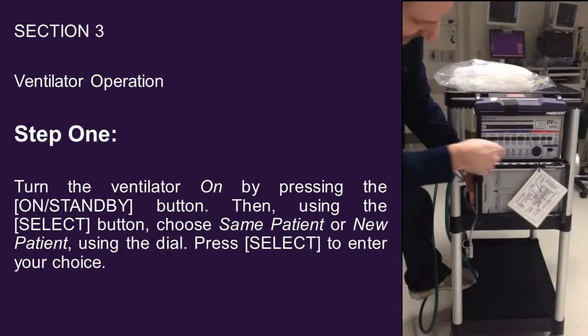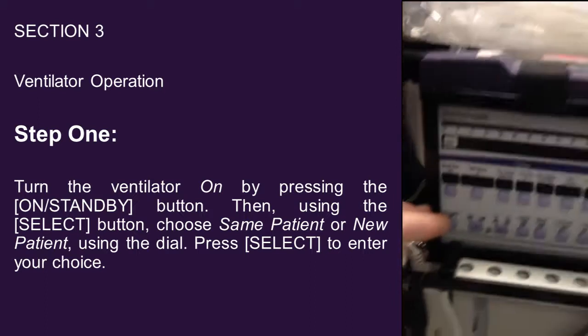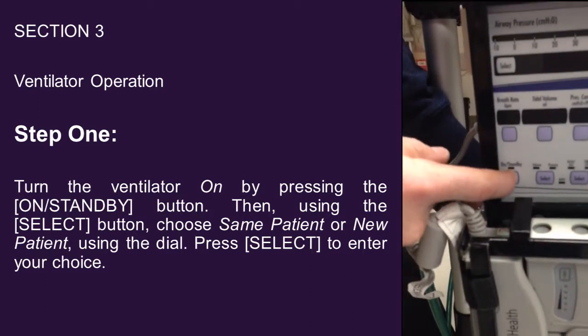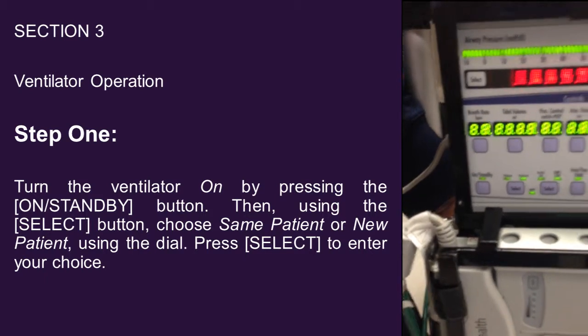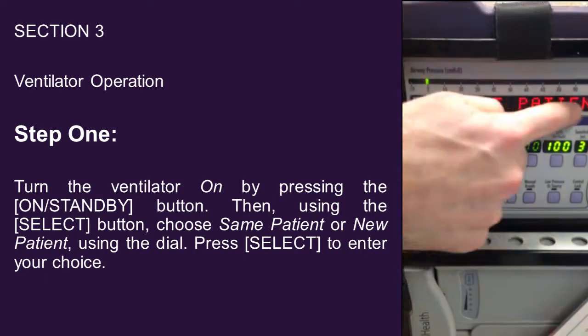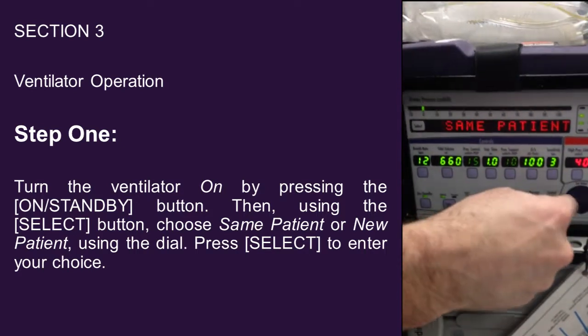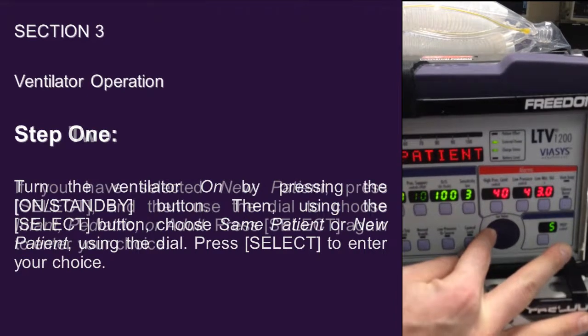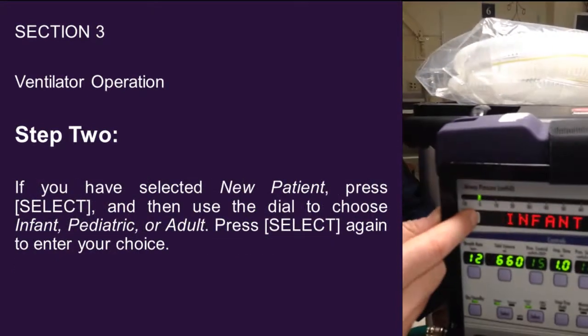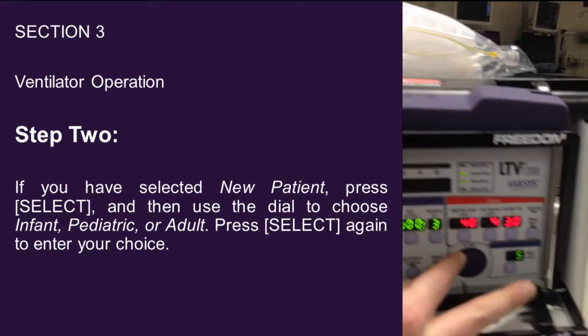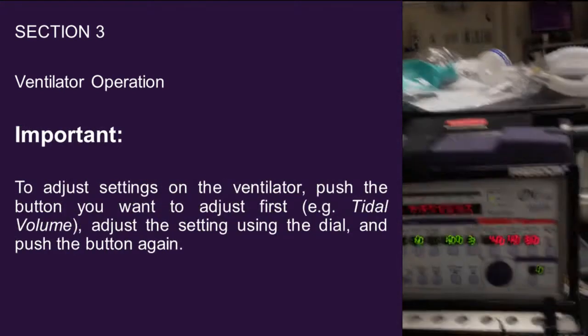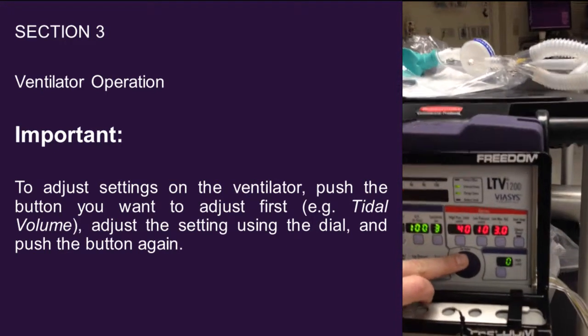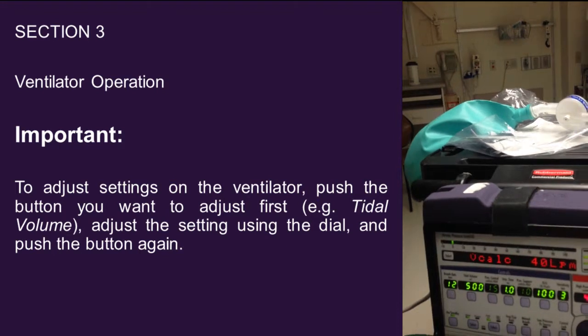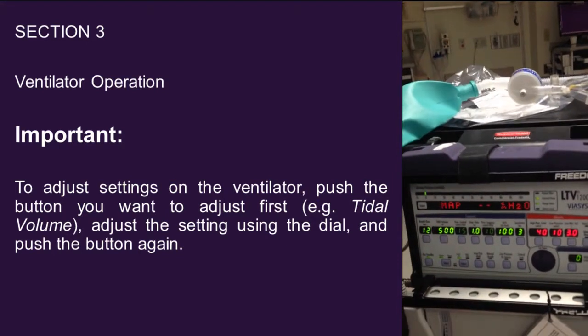Ventilator has an on-off switch, which is actually right here, which says on and standby. So you will turn on the ventilator, and then this tells you same patient, and then you can turn this dial to toggle between new patient, and if it's a new patient, press select, and you can decide whether it is an infant, pediatric, or adult. So we're going to say new patient. We're going to select adult. Select. And you'll see our test lung right here will eventually inflate. So the low pressure is going off because this isn't inflated. I'm going to silence that for a second.